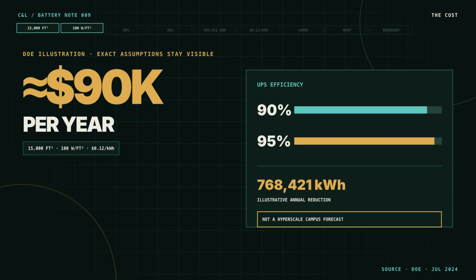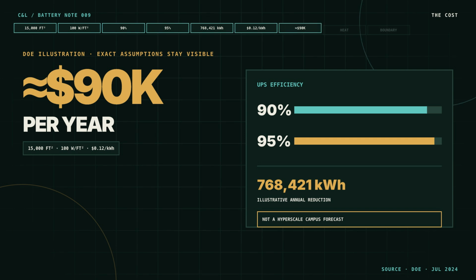The Department of Energy gives a bounded example: a 15,000 square foot data center with IT equipment operating at 100 watts per square foot uses 13,140 megawatt-hours per year for the IT load. Raising UPS efficiency from 90 to 95% would reduce the annual energy bill by roughly $90,000 at 12 cents per kilowatt-hour, while also cutting cooling demand. This is an illustration, not a forecast for an AI campus. Its value is the mechanism. Conversion loss becomes electricity expense, then becomes additional heat that the cooling system must remove. A buyer comparing batteries without comparing the complete conversion path can choose a lower sticker price and still accept a higher lifetime bill. Efficiency needs to be measured at the actual loading range, not only at a favorable nameplate point.